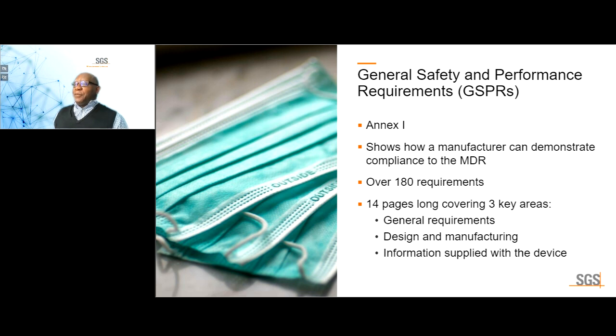Next will be the general safety and performance requirements. To my mind, this is the guts of the regulation. It's in Annex 1. That tells you everything you need to know. It's pretty comprehensive. It shows how a manufacturer can demonstrate compliance with the MDR. There are over 180 requirements. It's about 14 pages long, covering three key areas: general requirements, design and manufacturing, information supplied with the device. We'll go through this very quickly.